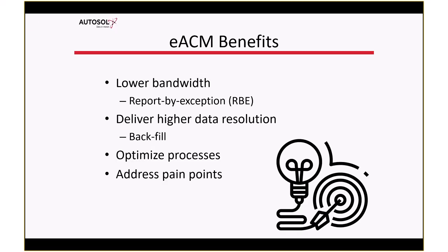So the benefits of deploying eACM is lower bandwidth, so you get that report by exception that we just saw the charts for. That's an enhancement to existing systems. Then you get something that we can't currently do with traditional SCADA systems, at least for remote sites in the oil and gas industry, which is a higher resolution data backfill. So what is happening in the field between each one of your hourly polls or each one of your 15-minute polls? Well, eACM can backfill that data for you for tags that you deem valuable, like a pressure or a flow. eACM can also act as a broader platform for edge processing as well.